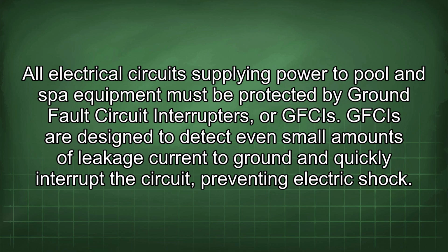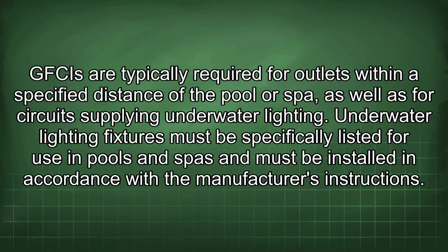All electrical circuits supplying power to pool and spa equipment must be protected by ground fault circuit interrupters, or GFCIs. GFCIs are designed to detect even small amounts of leakage current to ground and quickly interrupt the circuit, preventing electric shock. GFCIs are typically required for outlets within a specified distance of the pool or spa, as well as for circuits supplying underwater lighting. Underwater lighting fixtures must be specifically listed for use in pools and spas and must be installed in accordance with the manufacturer's instructions.